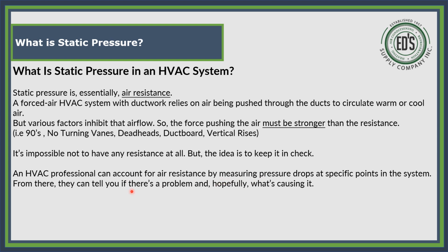Now, what is static pressure, you may ask? Well, static pressure is essentially air resistance. A forced air HVAC system with ductwork relies on air being pushed through the ducts to circulate warm or cool air. But various factors inhibit that airflow. So the force pushing the air must be stronger than the resistance, i.e. 90s or no turning vanes, deadheads, duct boards, vertical rises, etc.